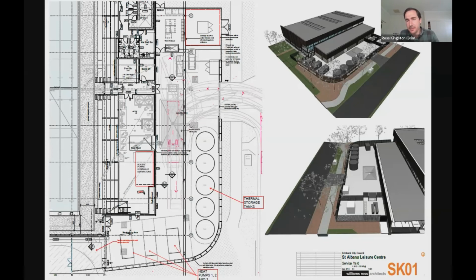The heat pumps like to be utilised depending on how they're sized, around 70 to 80% of their capacity. That's their optimum efficiency. So by adding additional demand during the solar PV generation hours, we're increasing the time they can run at that optimum efficiency, and minimising their usage outside of those hours.